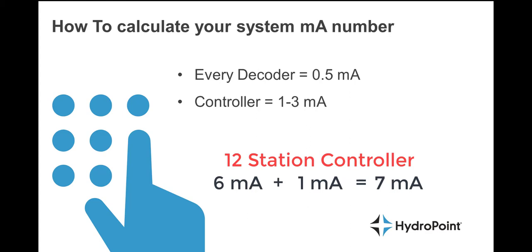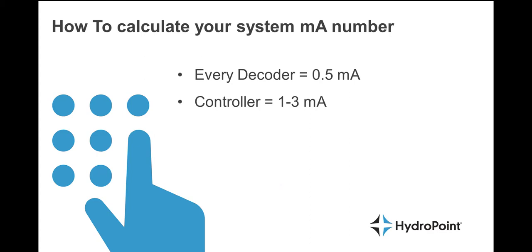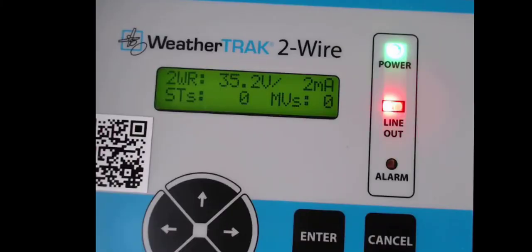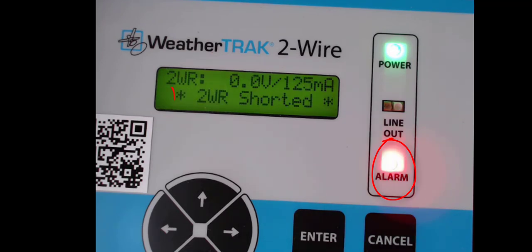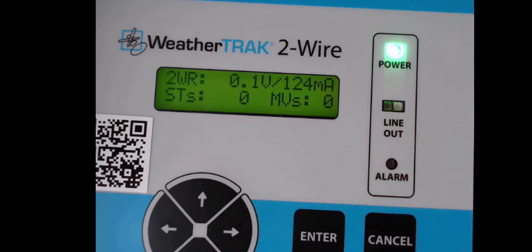But if there is any inconsistency in the wire, that number will start to rise. For every milliamp above this baseline reading, you are recognizing a place in the system that is weak and might eventually fail. So the first thing to do when troubleshooting a 2-Wire controller is check the alert interface for any alert notification, like '2-Wire shorted.' If there is an alert notification or the system is reading a higher milliamp reading than expected, then there is an issue with the 2-Wire path.